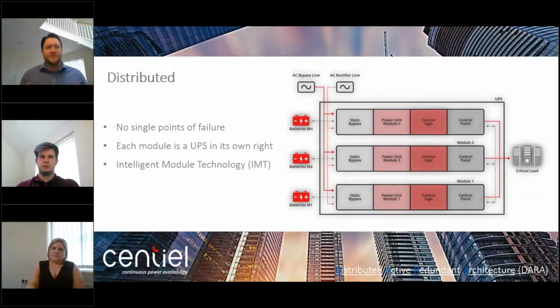Effectively, a UPS module is a UPS in its own right. You can take it out of the actual UPS system, cable it up, and it will behave as a standard UPS. So it's not just the physical side of things - we use another acronym called Intelligent Module Technology.